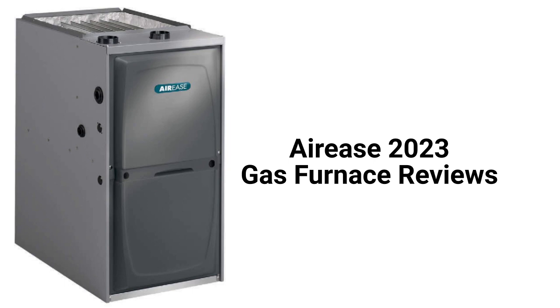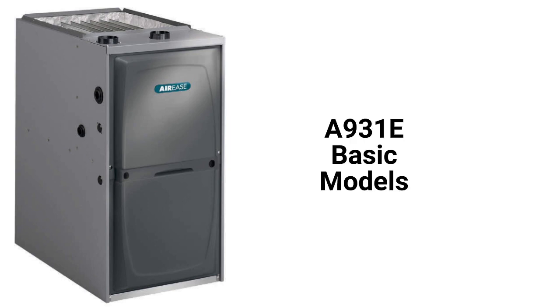They use hot surface ignition with silicon nitride igniters, which is quieter and more reliable than spark ignition. The A931E model is a basic gas furnace with a 93% AFUE efficiency and a constant torque blower motor.